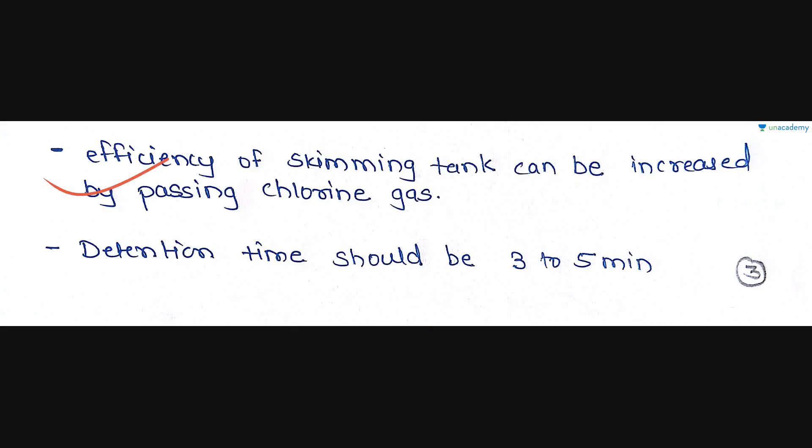The efficiency of the Skimming Tank can be increased by passing chlorine gas at 2 mg per liter of sewage along with the compressed air. Chlorine may also be added as a solution with the sewage discharge just ahead of the air diffuser plates. The action of chlorine is to destroy the protective colloidal effect of protein which holds the grease in emulsified form.